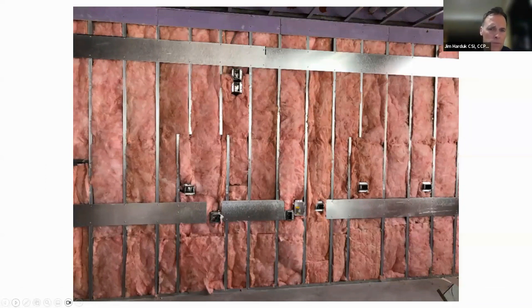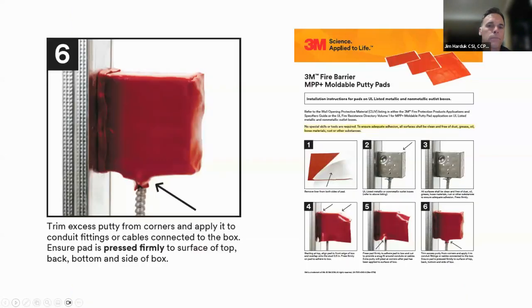So here's an example of a job where there were multiple outlet boxes, and basically we had over 100 square inches in 100 square feet of wall. So all of those outlet boxes would require a putty pad or some other type of protection on the backside. Next slide. And again, we have installation instructions for the putty pads as seen here. Next slide.